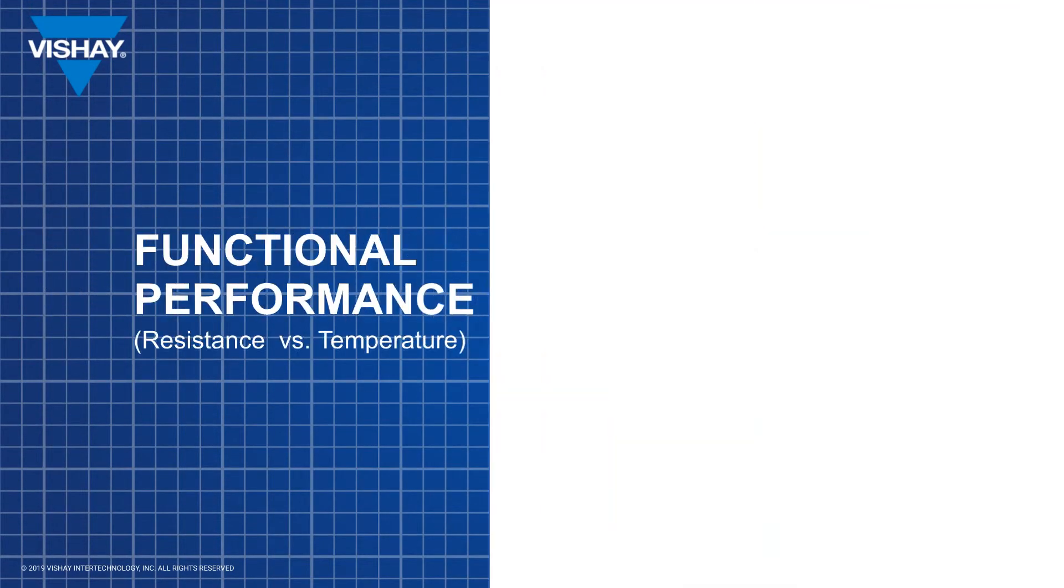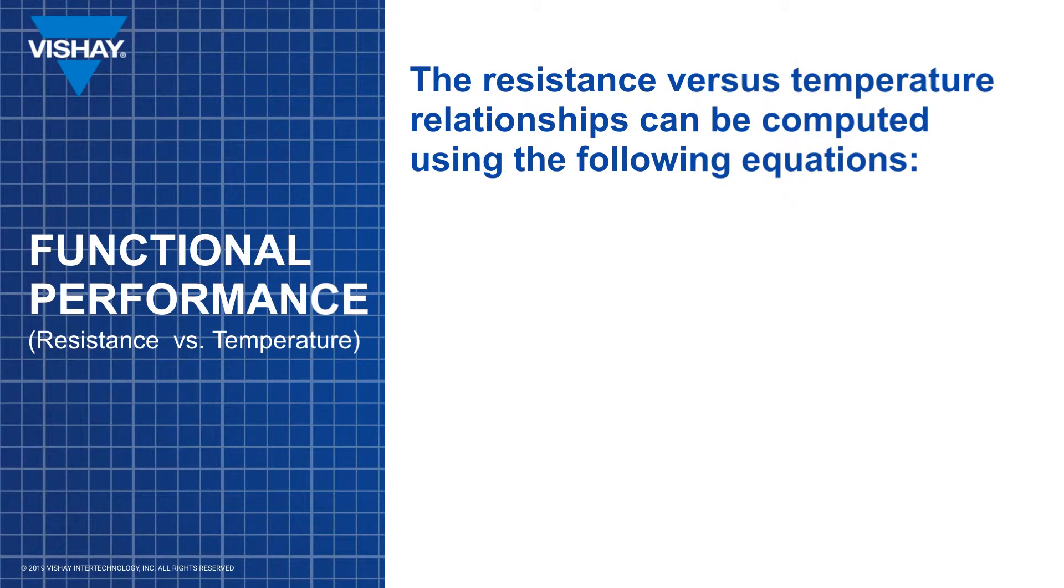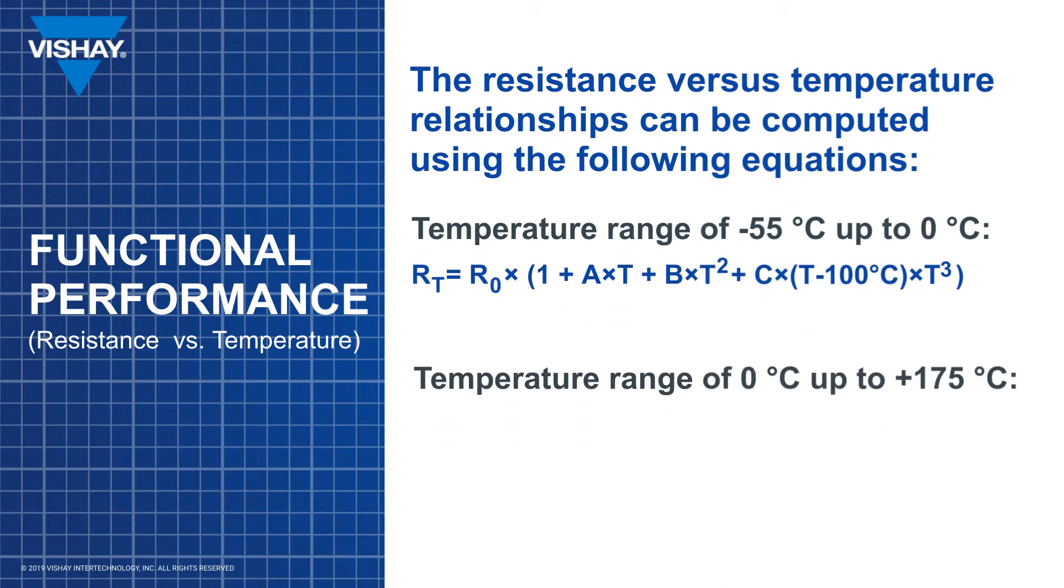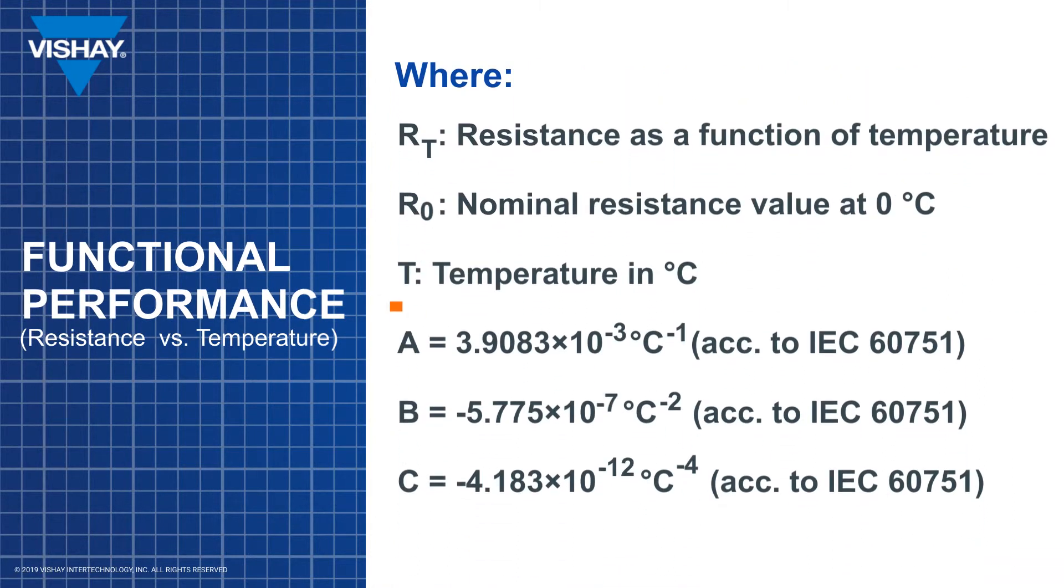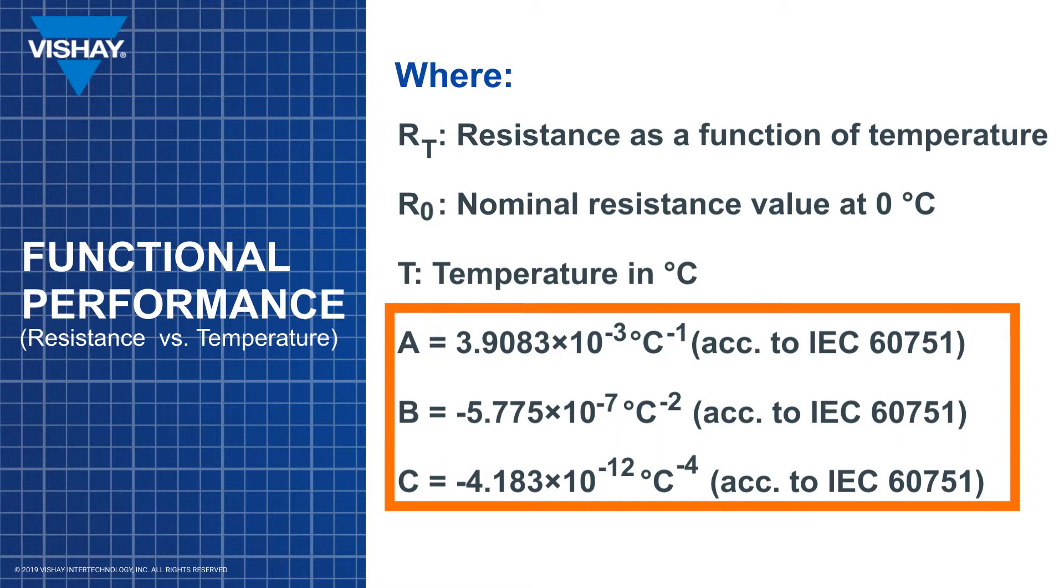The nearly linear resistance versus temperature relationship for the PTS-AT sensor shown above is accurately modeled using the set of equations outlined above with the known values that represent nominal resistance at 0 degrees C. A, B and C represent the Callendar van Dusen constants that are derived from actual resistance measurements in accordance with IEC 60751.